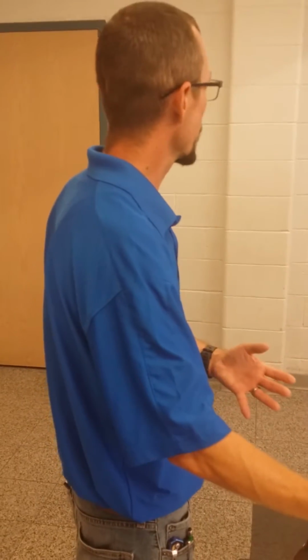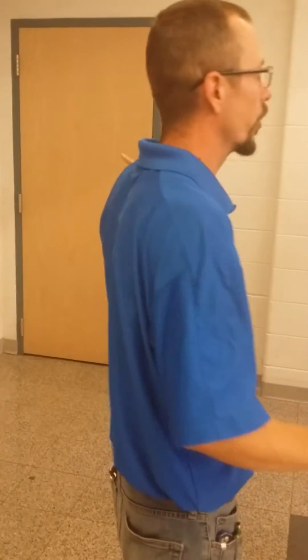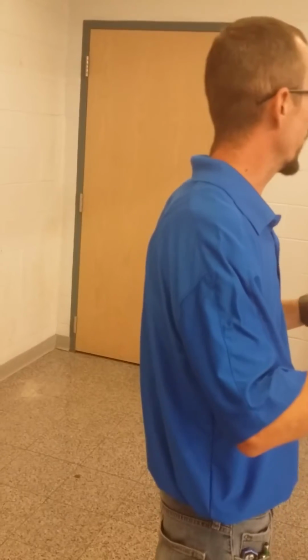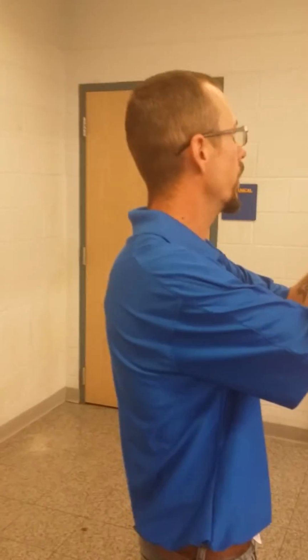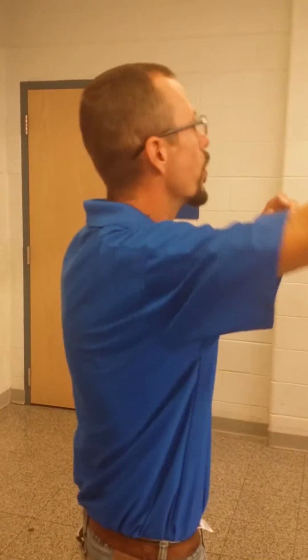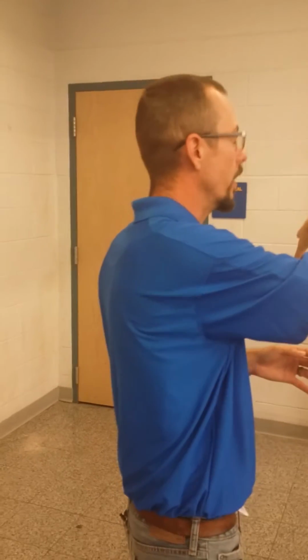Okay, you have a chilled water and hot water coil for these. Chilled water for conditioning or air conditioning, climate control, and heating for your hot water coil. As long as your boiler plant is up and running, those water valve actuators are going to open and say, I want hot water to run through here. Based on that need, that fan motor is going to come on and blow warm air into the conditioned space. Same thing with your chilled water coil, with the exception of we're not blowing cold air, we are removing heat from the air that already exists, taking it outside through your chiller to your cooling tower and releasing the heat outside.